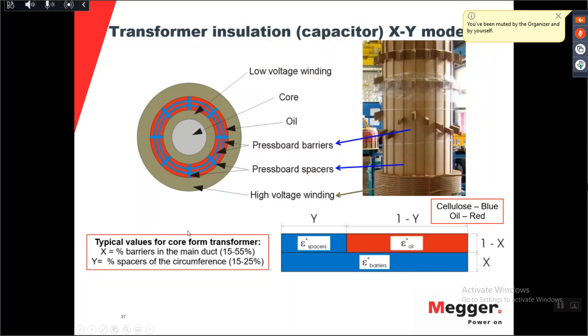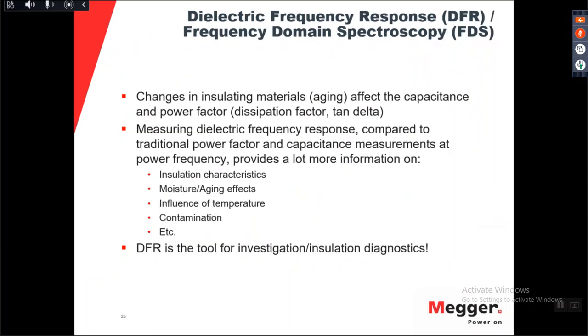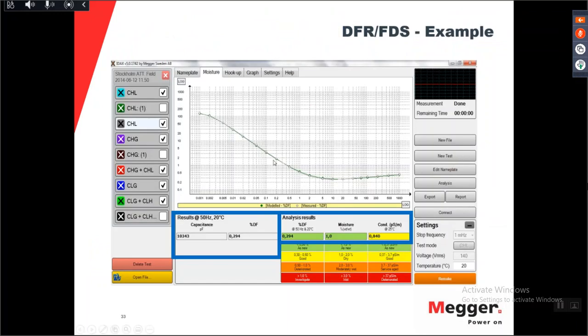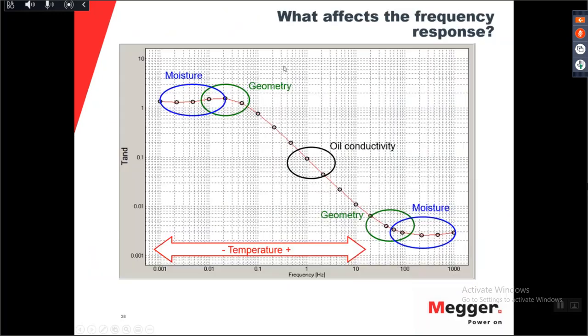predict how your transformer should look. So that is what you're seeing here. So we have taken the measurement, and you can see you have a model response, which is the green one. So you draw your own transformer with your particular moisture content, with your particular oil conductivity. And from that, you can say your transformer is very dry. It has only 1%. It's as good as new, on the verge of being very dry to moderately wet. So this is the classification from the technical brochures 342. Then you also have the conductivity of the oil, which means here, when the oil becomes worse, it becomes here. So this is what your model response looks like.